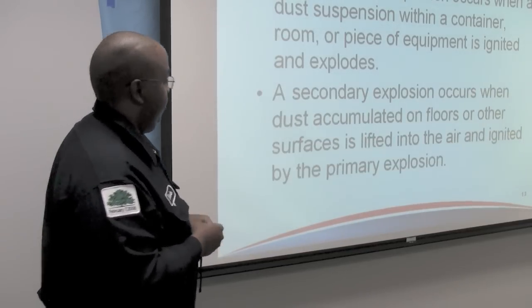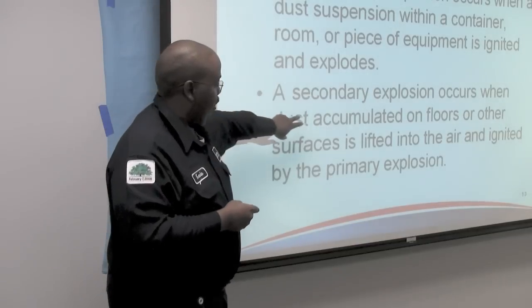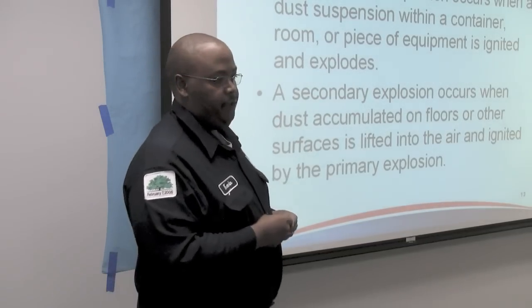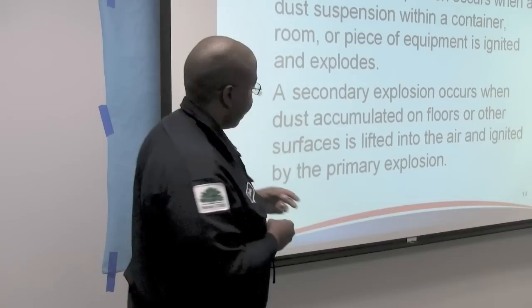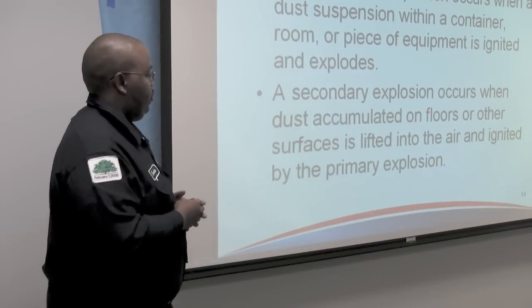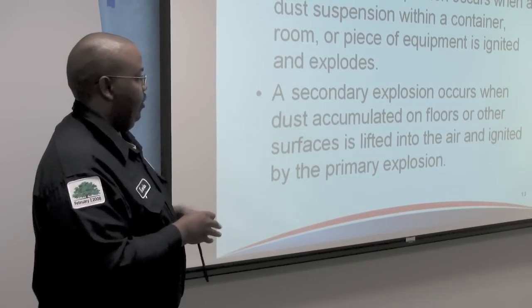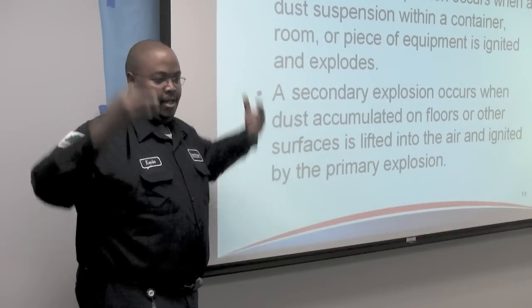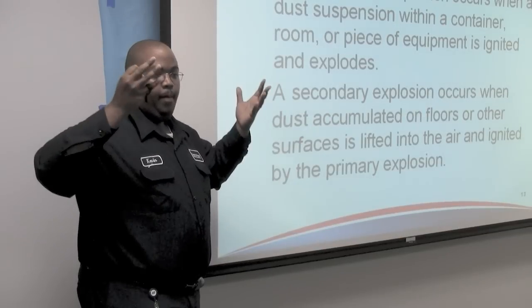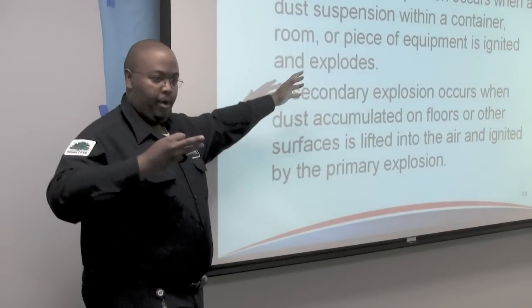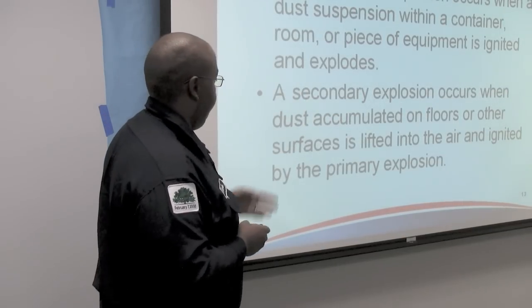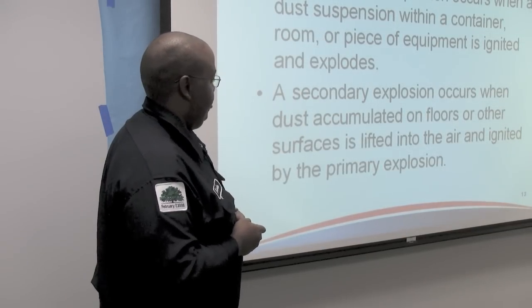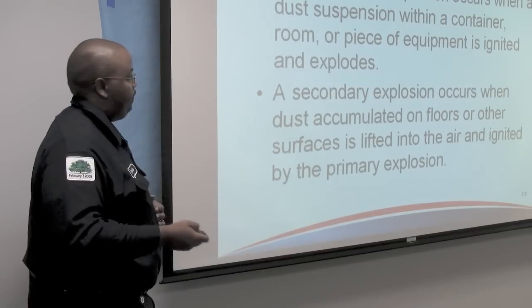The secondary explosion is generally the one that is more deadly and has more catastrophic results. It occurs when dust accumulated on floors and other areas — that unseen dust — is stirred up as a result of the primary dust explosion, and then is ignited in air.